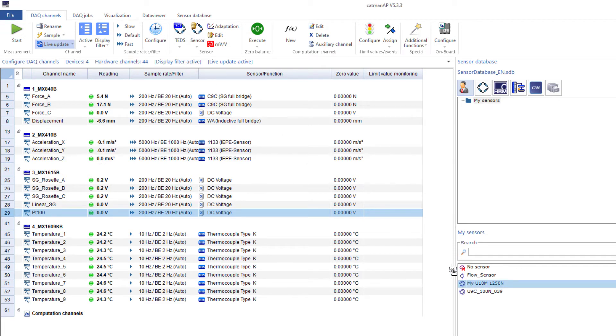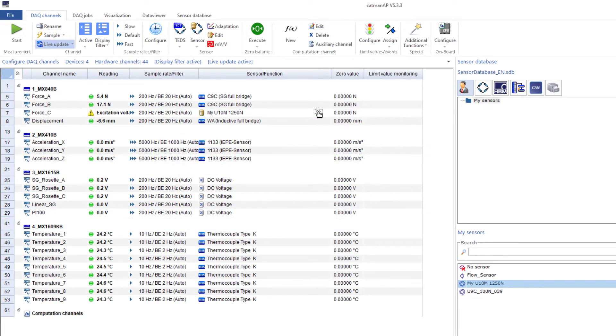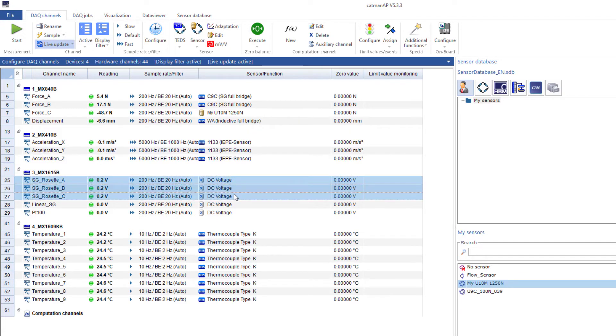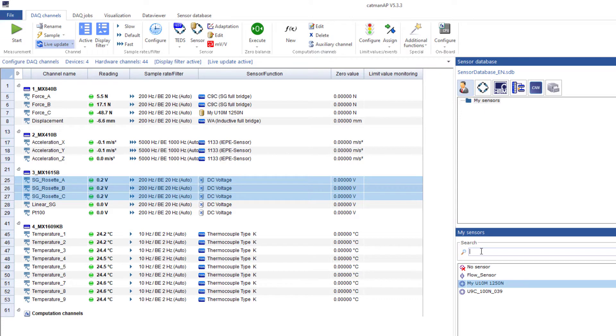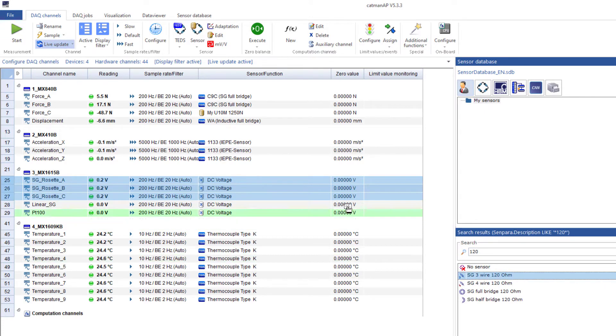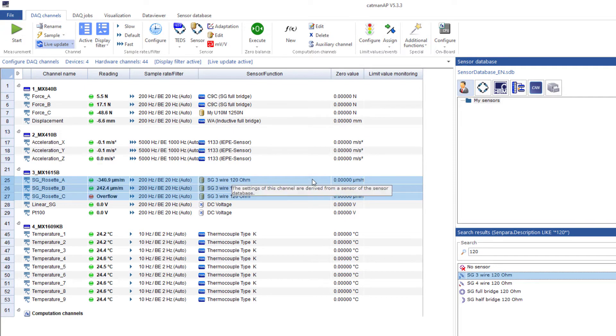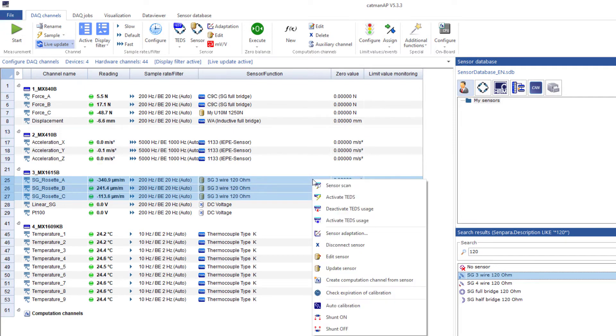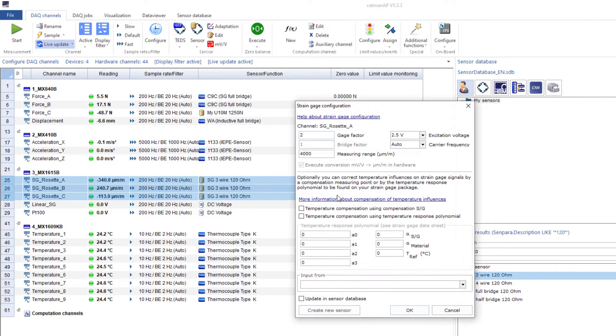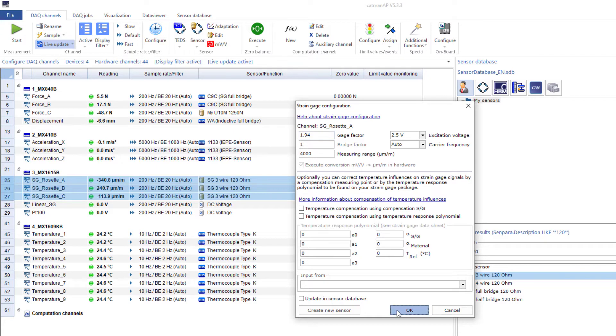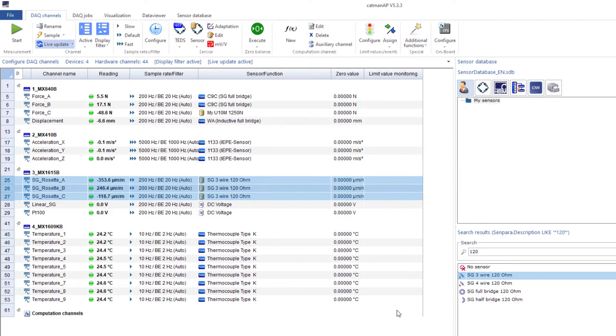I have already stored my U10M in the sensor database and can easily assign it by drag and drop. The three strain gauges of my rosette have 120 ohms. I'll create them from the sensor database. I'll now store the gauge factor of this rosette in the sensor adaptation dialog. This setting is applied to all three channels. Hence, the configuration is very quick and clear even if you have a lot of strain gauges.